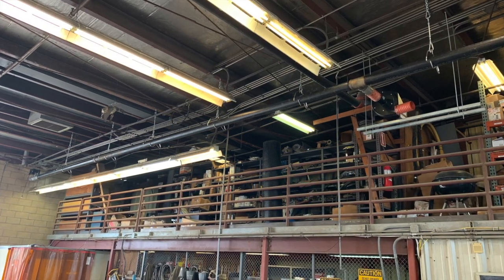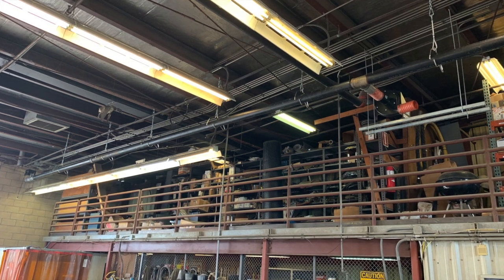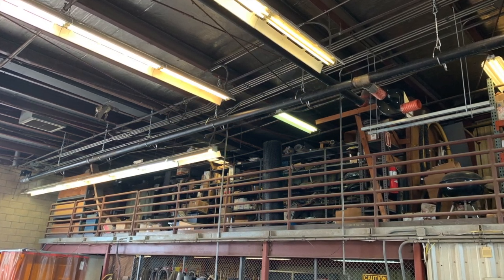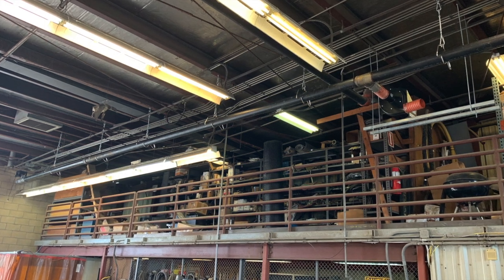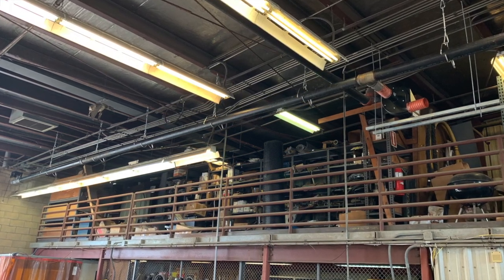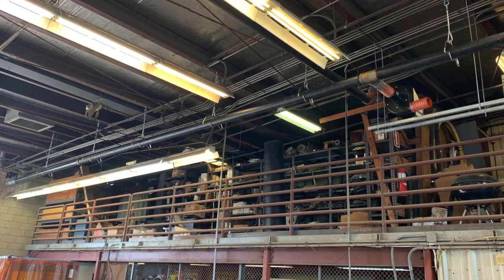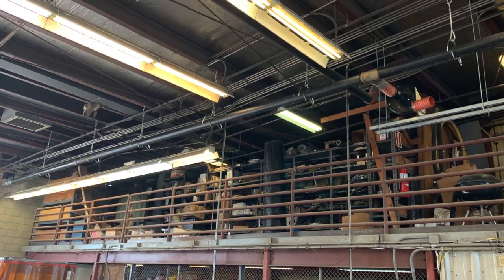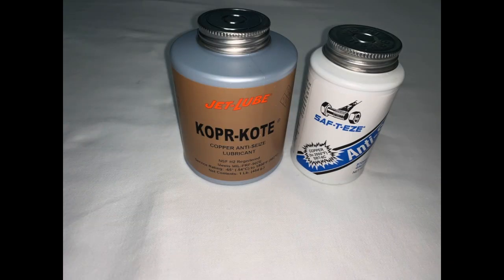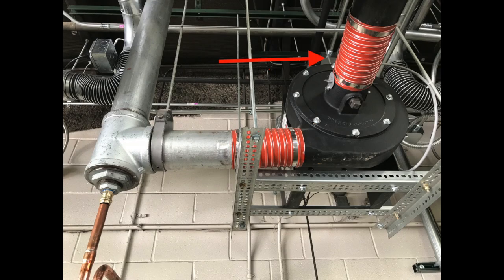The Schedule 40 pipe is threaded and not welded in order to prevent welding overhead of shop personnel. This piping for the heat exchanger is not pressure tested and will only be under -3 inches water column. We want all the joints watertight, but not loose. Overhead Products supplies the high temp joint compound for every threaded joint on the system. A small amount of high temp compound goes a long way. Once the joints are screwed together watertight, wipe off the excess high temp compound. This will minimize the dripping when first firing the system.